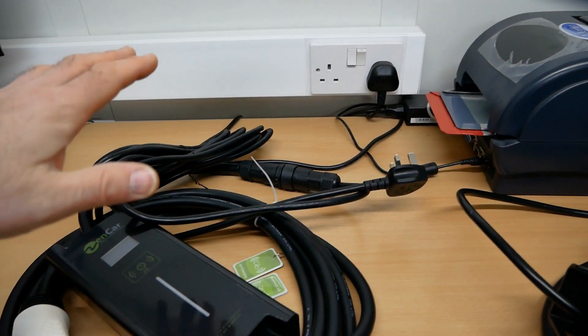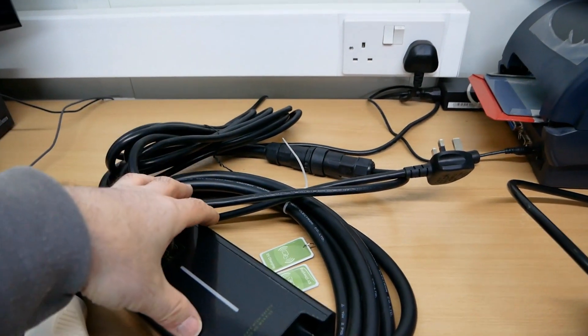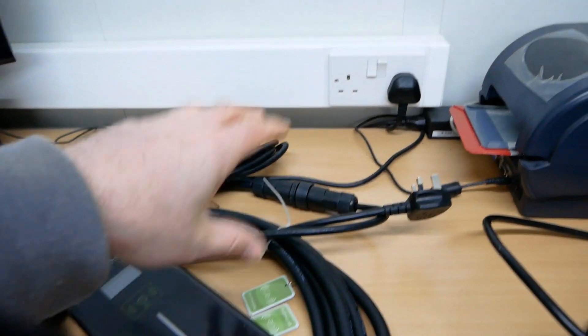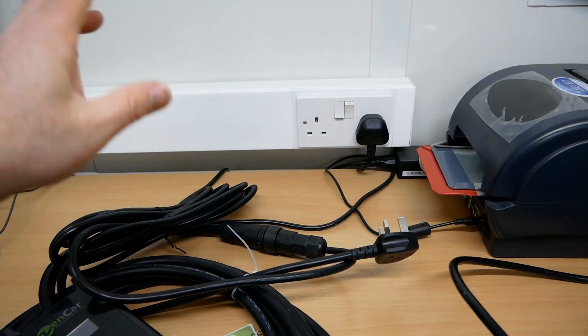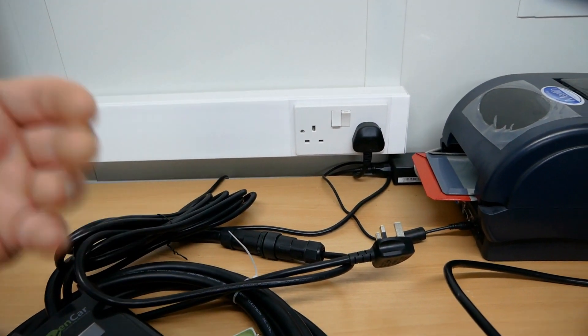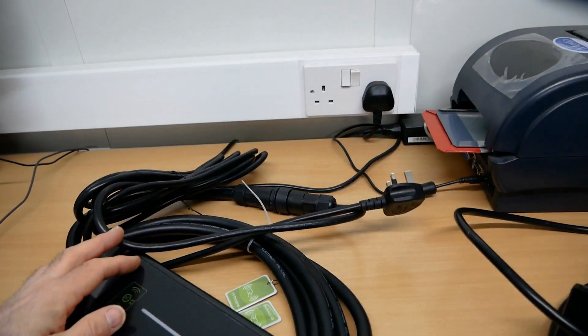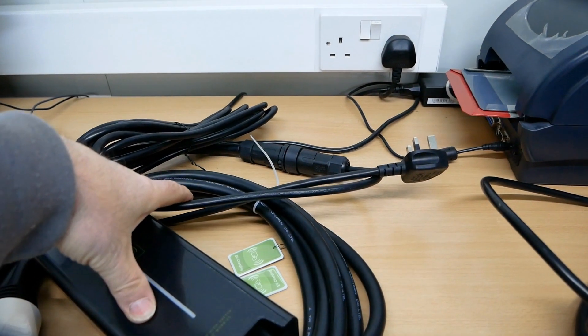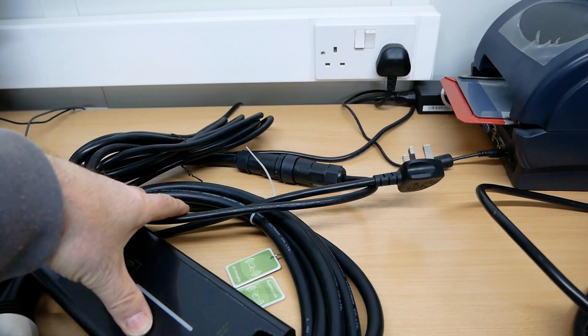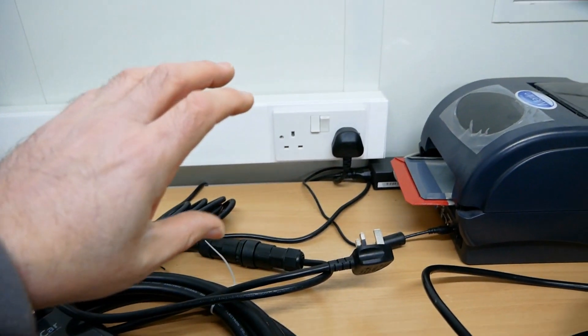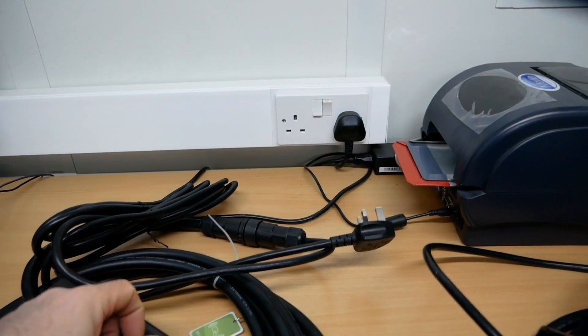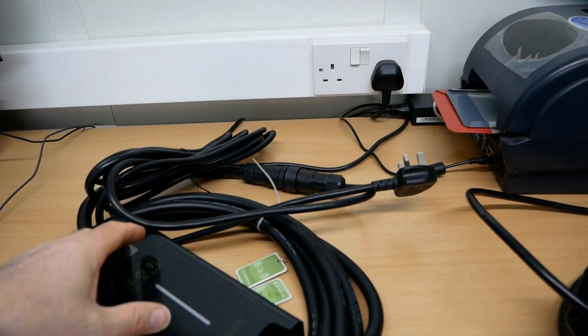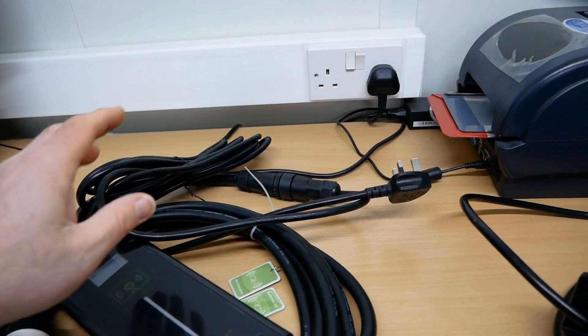So it's not necessarily a fault of the granny cable. The fault was there on your wiring anyway, it's just this is going to find it. That's why granny cables are capped at 10 amp, just so it doesn't stress your wiring so much, and that's also why you shouldn't use extension cables.